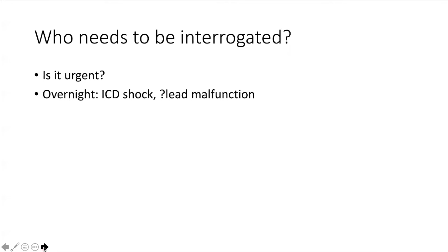When you get called to interrogate a device, you really need to first ask the primary service to identify the type of device they have. And you must have the proper programmer to perform the interrogation, because each company has their own programmers and they don't intermix. For example, a Medtronic programmer will not work on a Boston device. I'll just say as a side note before we get into this, you should really always feel comfortable when you're interrogating a device. Print out the information when you get it. If you have questions, go over it with one of the EP fellows and attendings later, or you can always call someone overnight.